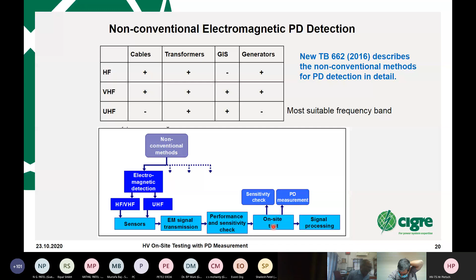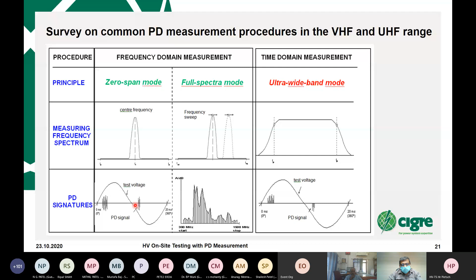Very important is that in these frequency ranges, different techniques are available. You can make a so-called zero span, like listening to the radio - PD music, as we defined it internally several decades ago - or make full spectra. Then you down-convert it to a PD pattern, and correlate it with a sine wave to see where the PD activity is - its position relative to amplitude, zero crossing, and so on - which gives important hints about the kind of defect you have.